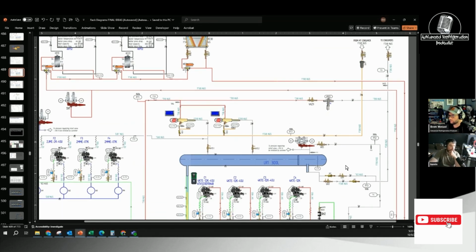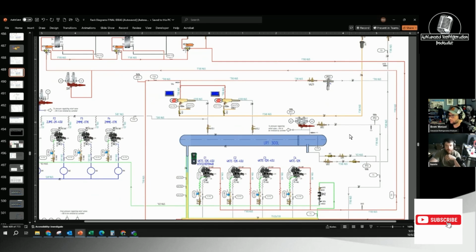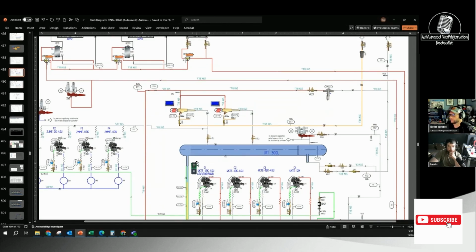Yeah, it's just dump it. At that point, your only load on the rack or the compressors is your actual flash tank pressure. That's it. Yeah, and your low temp blowing into them too, right? The low temp's going into the flash tank. Yeah, but it's still got to take the vapor off of that, whatever it's going to vaporize. Like, the only load is the flash tank at that point. Oh, okay, I see what you're saying. Yeah, so you're only pulling off the top of the flash tank, which you're less likely to flood out with the load off the top of the flash tank.